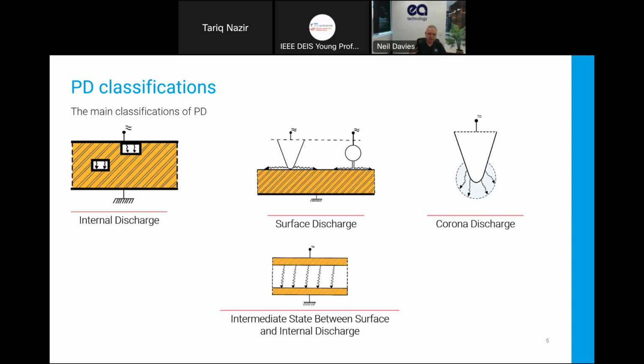And it characterizes quite differently to internal discharge. Often you're going to get relatively low levels of amplitude of discharge, but lots and lots of pulses of it. So if you look at the picocoulomb range, whilst you might get hundreds or thousands of picocoulombs in an internal void as it builds up and collapses, on surface discharge a serious level of discharge can be down in the tens of picocoulombs, and it is greatly affected by the environmental conditions. So it's two very different characteristics of partial discharge activity.